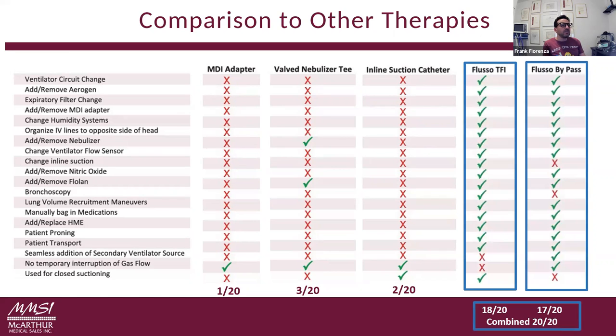If we add either device - if we look at Flusso TFI, it'll keep the circuit closed for 18 out of 20. If we go with Flusso bypass, it's 17 out of 20. And the design of both devices works off a different mechanical principle, you can see that the X's don't line up. So that's where the combination of the two devices, if you really wanted to block all reasons why you disconnect, you'd be looking at 20 out of 20 reasons that could be avoided. But either device on its own gives you a very dramatic increase in keeping the circuit closed.